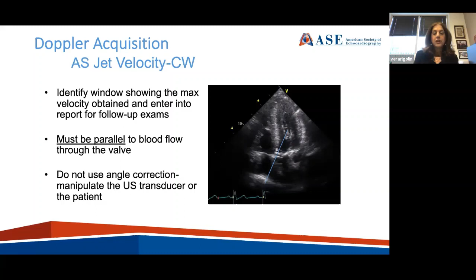We want to do it in multiple windows. These are the windows with the 2D transducer. These are the windows with our non-imaging transducer. I would also include the apex here. We want to adjust the gain and the scale to optimize our signal. We want to acquire the spectral Doppler images at a slower speed to show at least 3 complexes, and then at a faster speed to actually do the measurement.